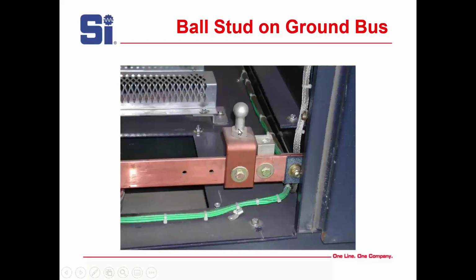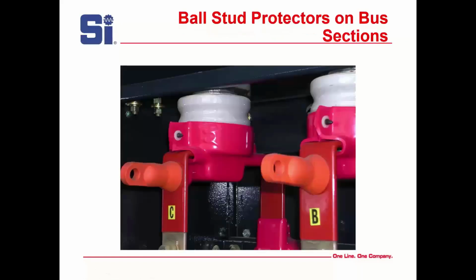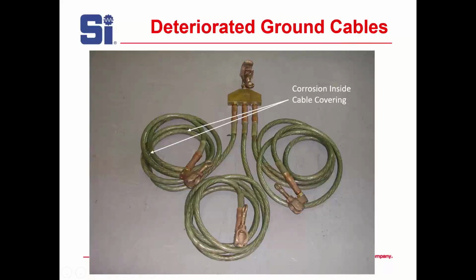And you get them in different configurations. They actually have extended ground studs now, where it has to be longer. They have longer ones. And what I really like about them is that you can put an insulating cover over them and not have any problem with metal-clad switchgear. Good stuff. Now, here's one that's got some corrosion. You can see it darkening in here. It's starting to corrode. The impedance of it may not be affected at this point, but it's something you have to watch.